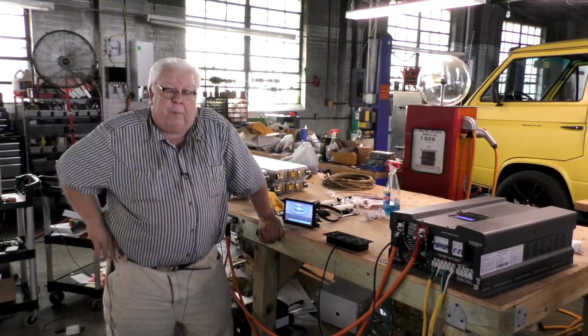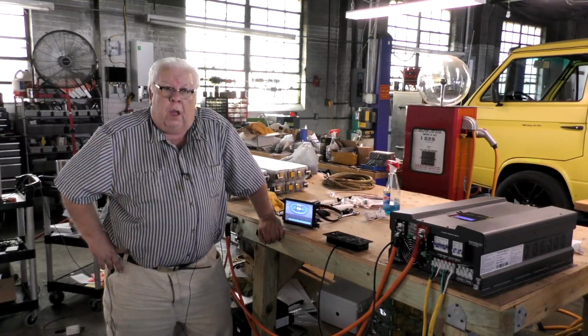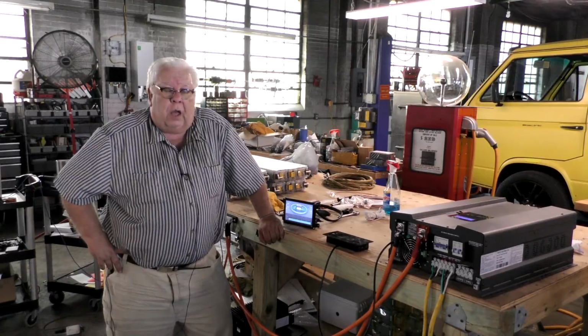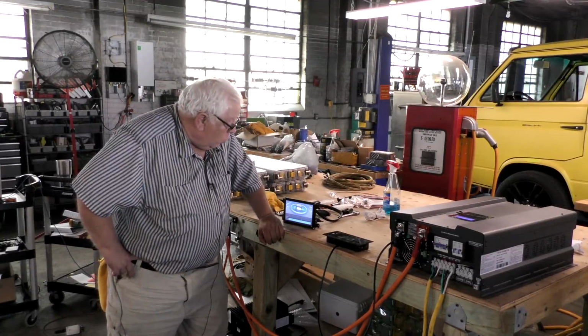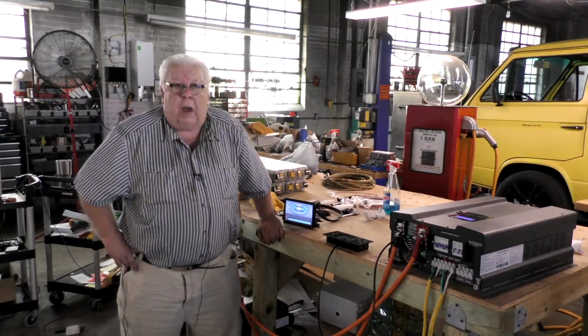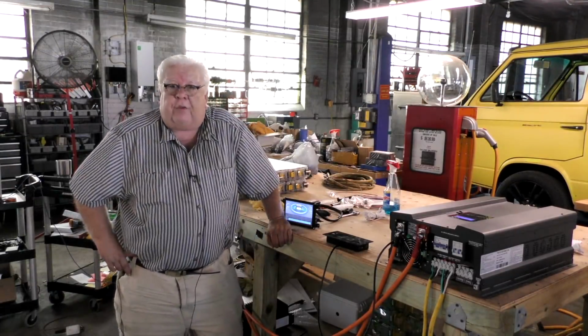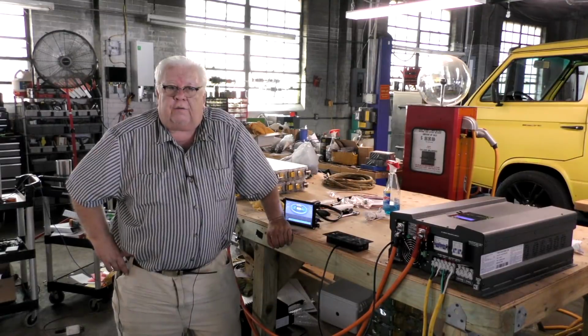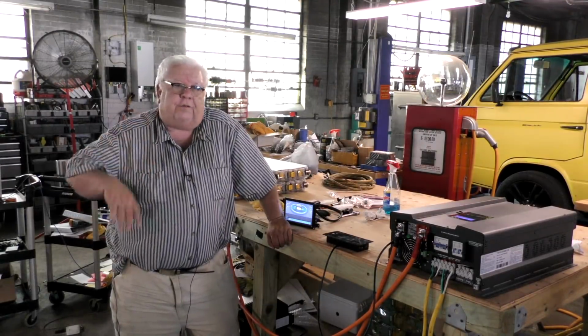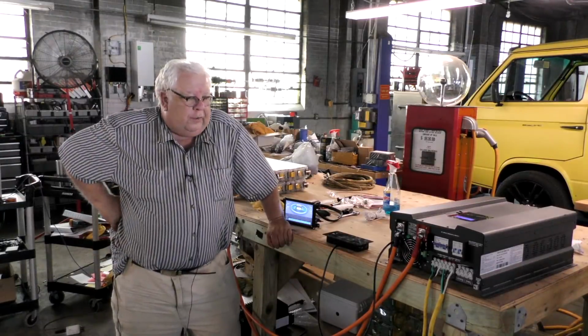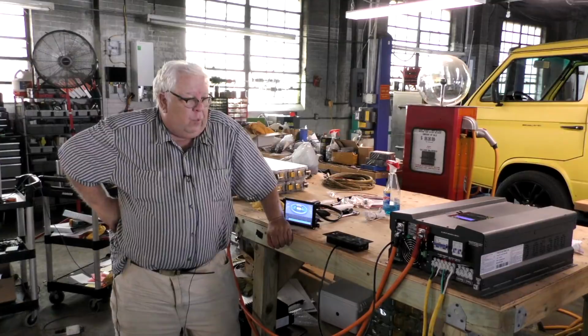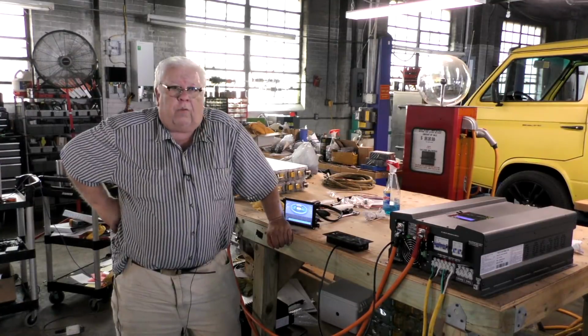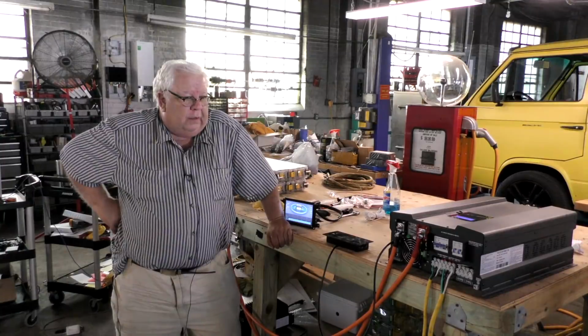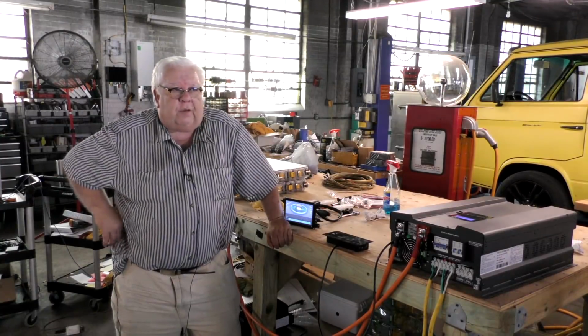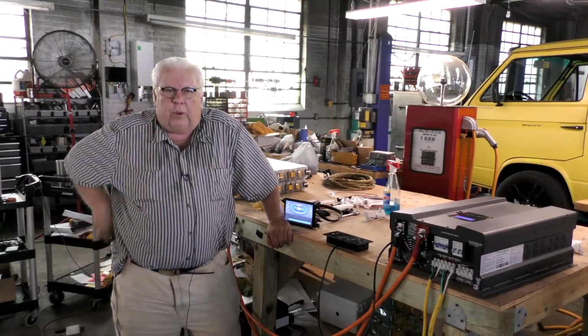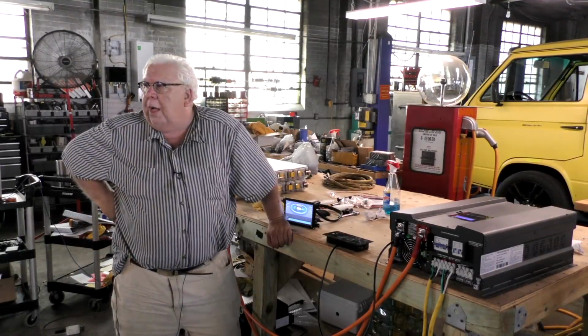Everything was running. The battery terminals were getting warm. I'm setting the temperature cutoff at 55 C. Right now we're at 39, so not a big deal. But if you run it for an hour or two at 100 or so amps, that temperature starts to crawl up. We're going to do a big project once this testing is completed on all the parameters of our 12 kilowatt inverter. I've had several inquiries from Puerto Rico and Costa Rica, and they're not too concerned about UL listings.